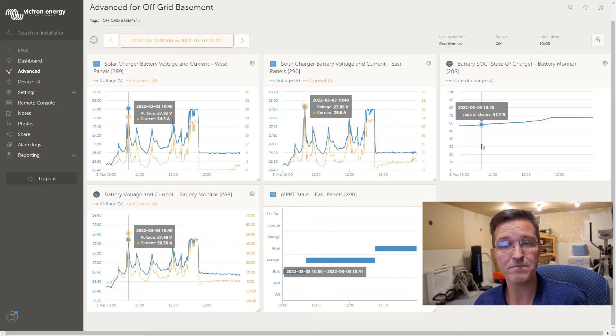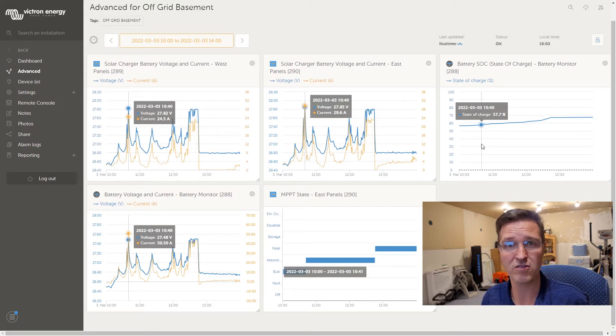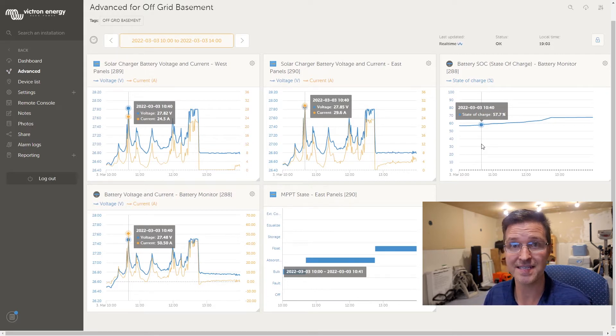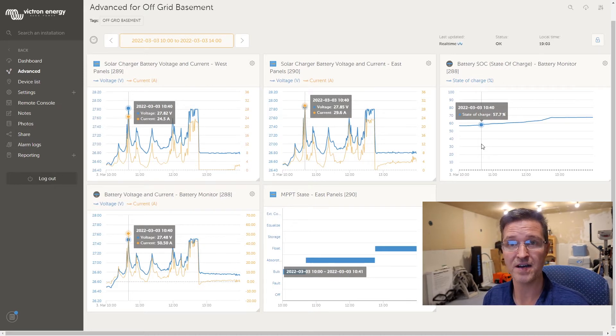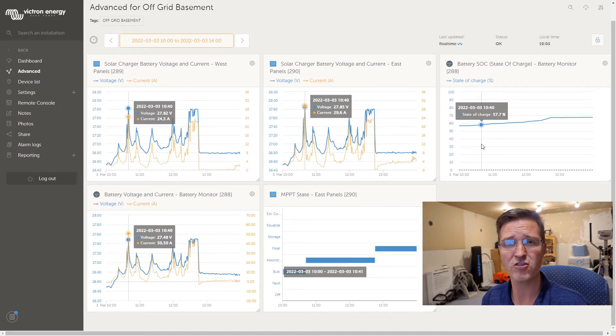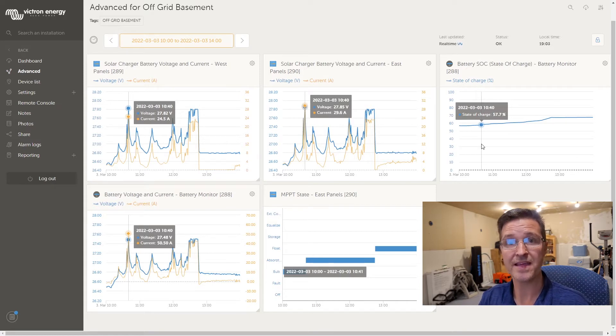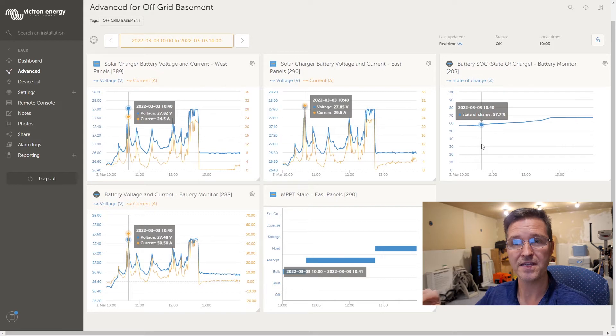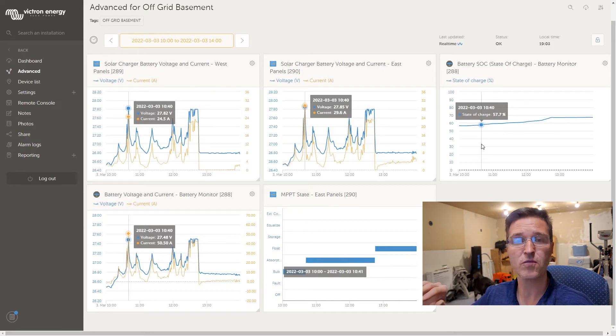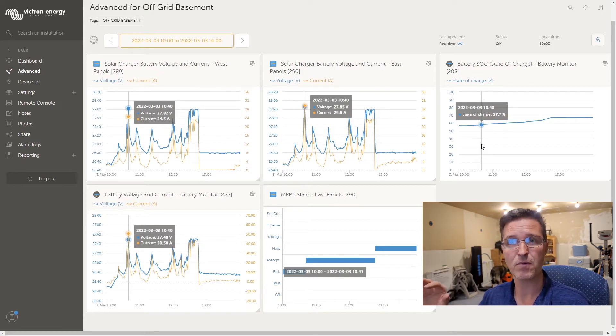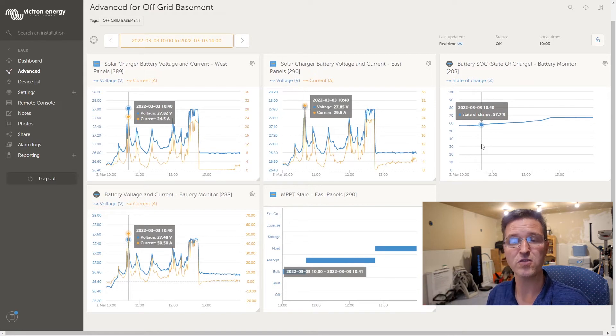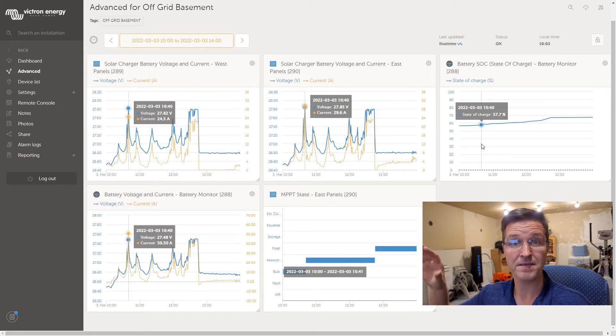So 27.48, I mean that is right in the middle of your charge cycle. If you've ever seen a graph of a lithium iron phosphate battery charging, it goes up really quick and then it levels off for a long time, and then it jumps right before it gets to about 27.75, 27.8 for a 24 volt system it will quickly jump up.